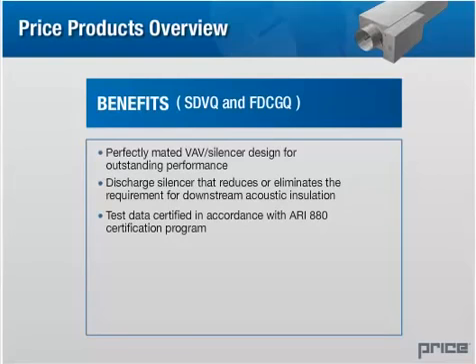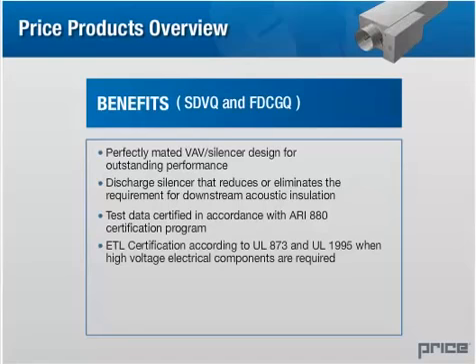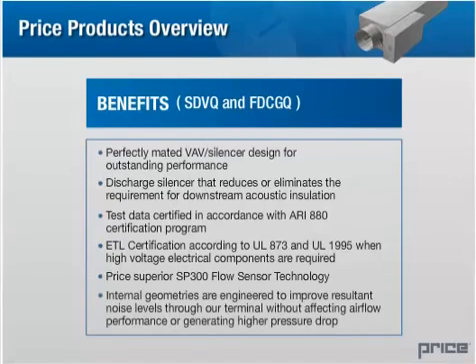program, ETL certification according to UL 873 and UL 1995 when high voltage electrical components are required, Price superior SP300 flow sensor technology, and internal geometries engineered to improve resultant noise levels through our terminal without affecting airflow performance or generating higher pressure drop. In the following section, we'll take a closer look at each of these terminals while examining their features and benefits.